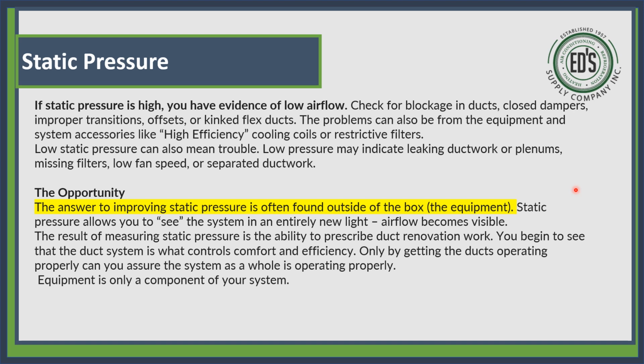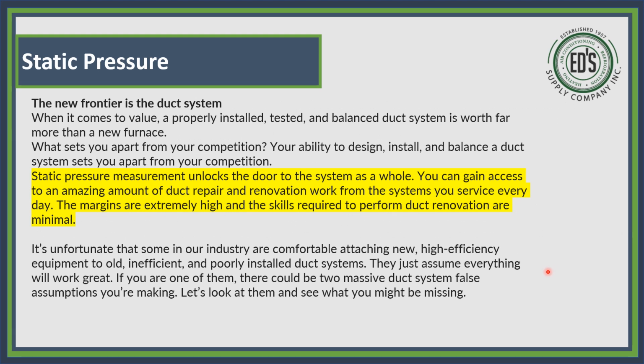But let's say you're doing a unit swap out. Take the opportunity and think outside the box, because static pressure will allow you to see the system in an entirely new light. Airflow becomes visible when you can read your static pressure and you know where the problem is. You can easily show the homeowner where the problem is and may get some extra work to fix the problem. Now, this new frontier in the duct system, when it comes to value, a properly installed, tested, and balanced duct system is worth far more than a new furnace.